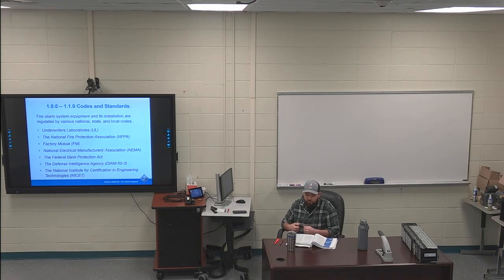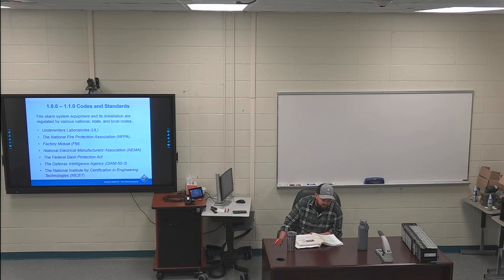Going into page 2 at 110, the standards organizations. On page 2, right before those bullet points, the following lists some of the many national organizations responsible for setting the industry standards. I've got the 4th bullet point highlighted, NEMA, National Electrical Manufacturers Association. This establishes standards for equipment. Not fire code stuff, but like you have your motor starters, like a NEMA size 1 motor starter, stuff like that.